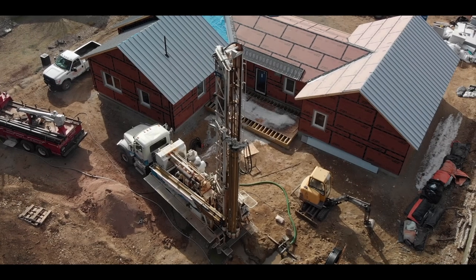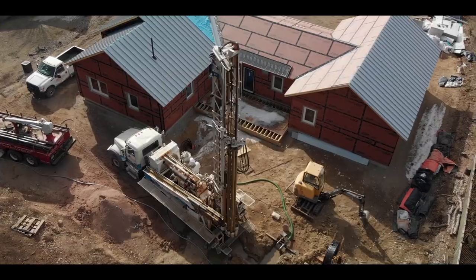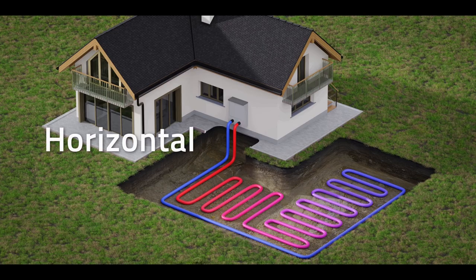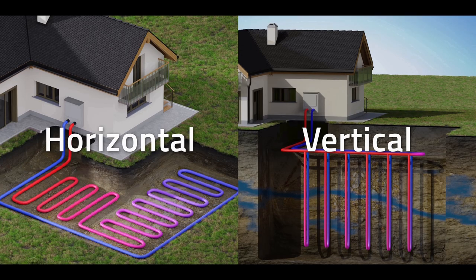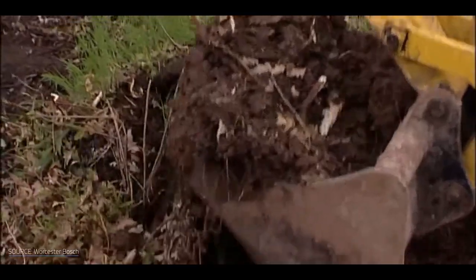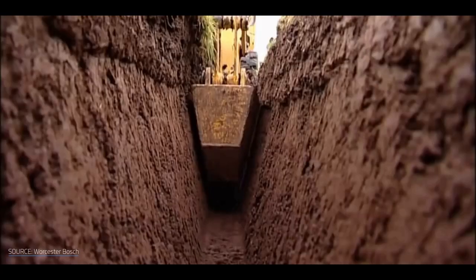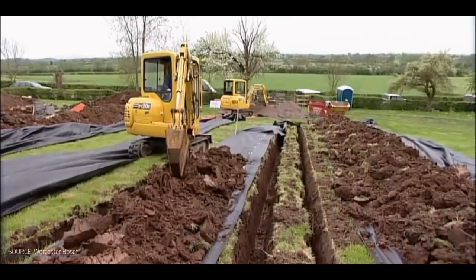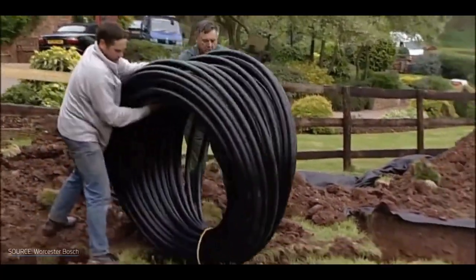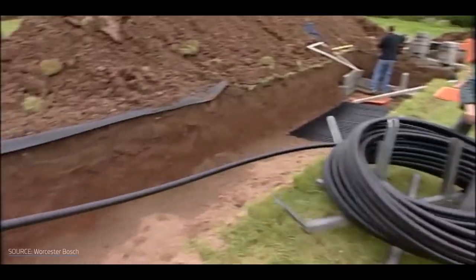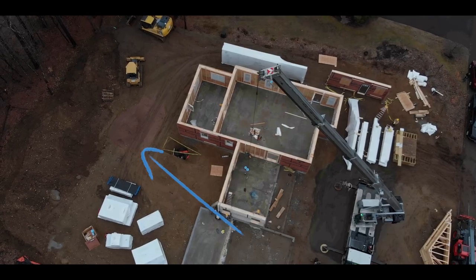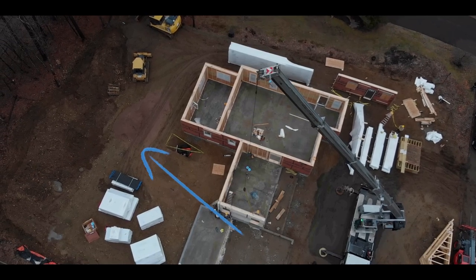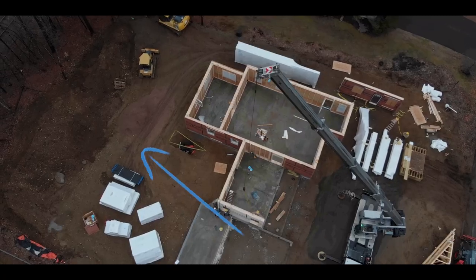But it's the geothermal well that I was crazy interested to see built out. There are two typical options for a ground loop: a horizontal loop and a vertical loop. The more affordable horizontal loop is where they dig down ideally 6 to 10 feet over a large area of your yard, then put in a single run of tubing in small loops that feeds back to the house and cover it back up. Given the size of my yard and its location, a horizontal loop wasn't the best option for us, so we had to go the more expensive route with a vertical loop.